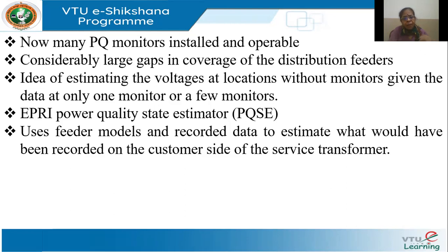So I can estimate the voltages at different locations without monitors, given the data at maybe one or more monitors, right? EPRI has developed a very good power quality state estimator model, and using this, the feeder models and recorded data are used to estimate what would have been recorded at the consumer side. That means I am not actually recording. See, I can't install a power quality meter at every consumer premise. That would be virtually impossible. Okay, so we'll think of the transformer. But then there are so many transformers at the lower level where the output of the transformer is directly fed to the consumer. So I can't obviously install monitoring equipment at every point in the transformer also. Therefore, we try to use the measurements we have, and try to make an estimate of voltages at points where we don't have the measurements.